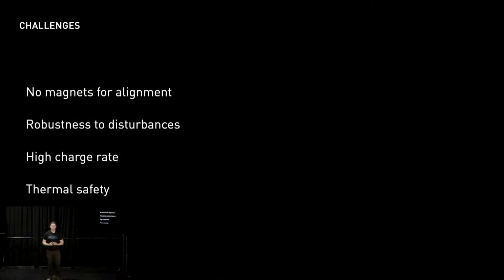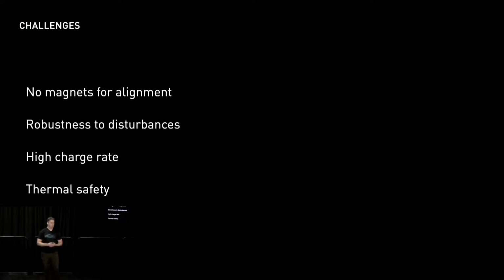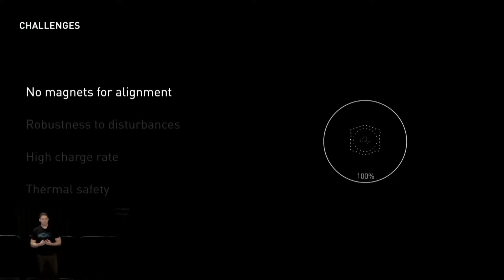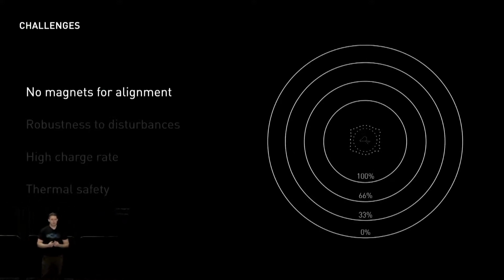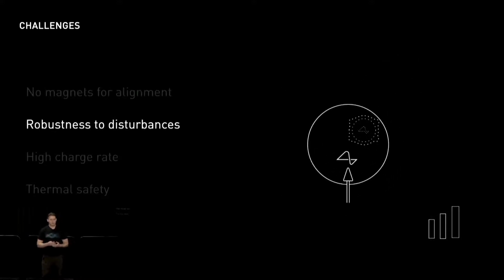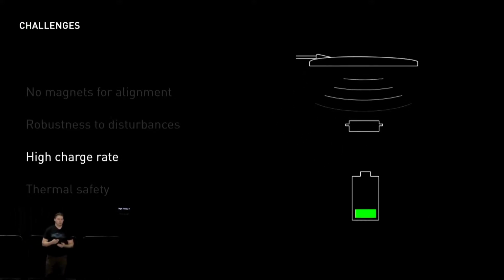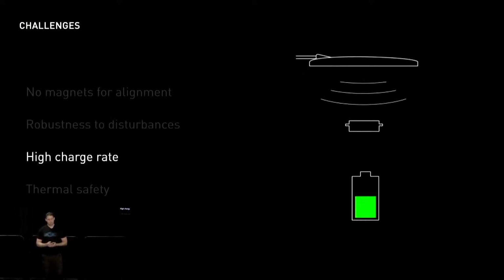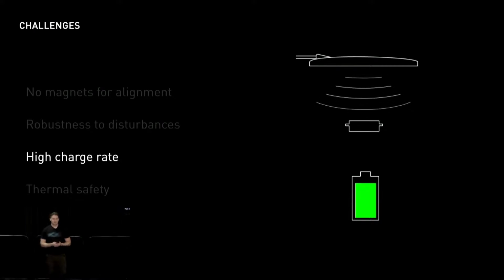However, unlike many consumer electronic devices which can simply offer a physical connector, charging a fully implantable device poses several unique challenges. First, the system must operate over a wide charging volume without relying on magnets for perfect alignment. The system must be robust to disturbance and complete quickly so as not to be overly burdensome. However, most important is safety.